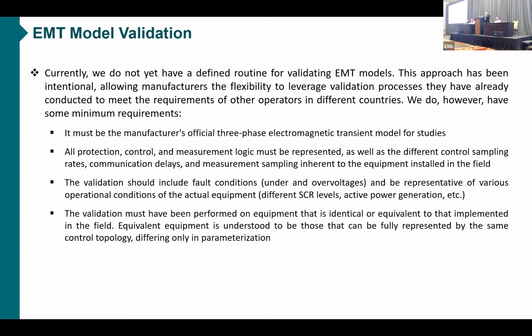Although it's really flexible, we do have some minimal requirements. It must be the manufacturer's official three-phase EMT model for studies. It can be a typical model. All protection, control, and measurement logic must be represented. So sampling rates, communication delays, and measurement sampling, which are inherent to the equipment, are very important for us.